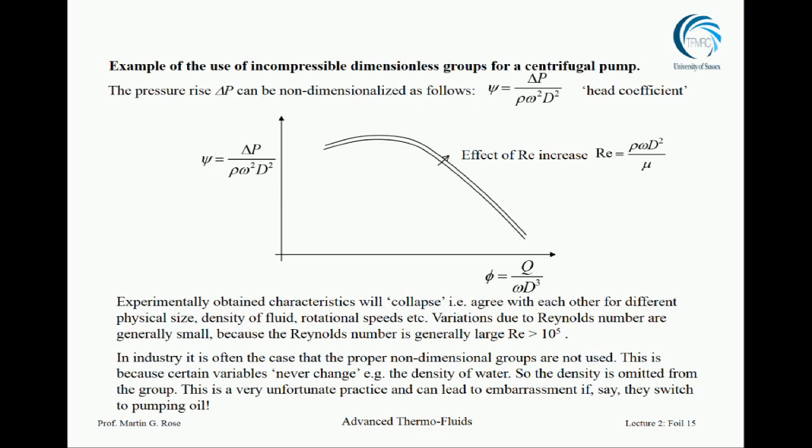The curve peaks in this graph at about 40% flow or so. There's a maximum. At the maximum, you're okay, you're just stable. But the pump is getting dangerous, it's getting unstable, it can't really be sure what to do next.